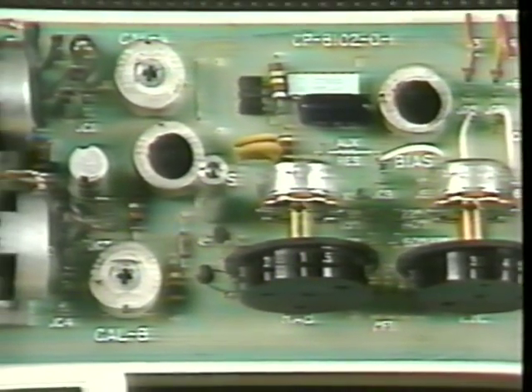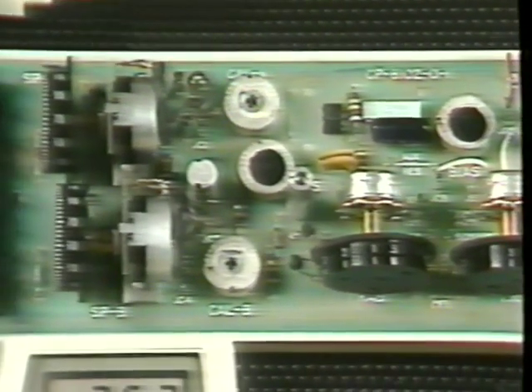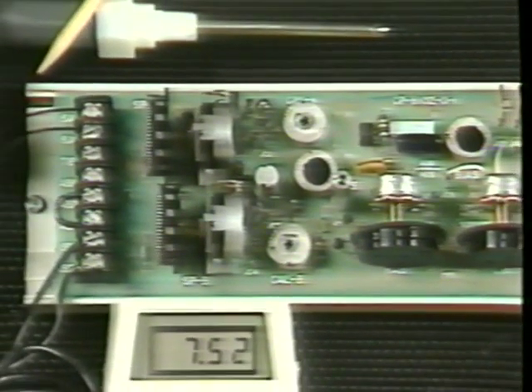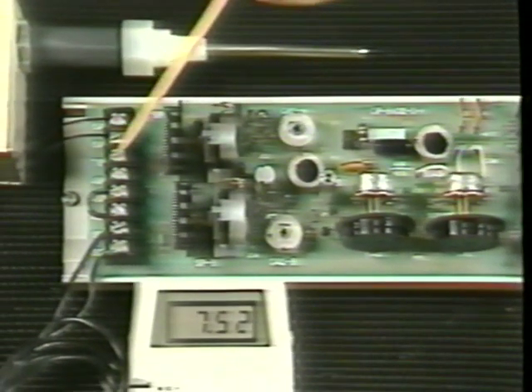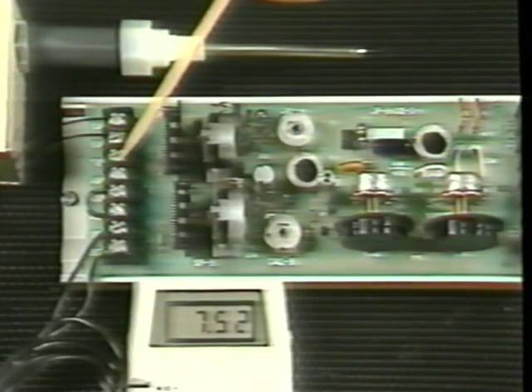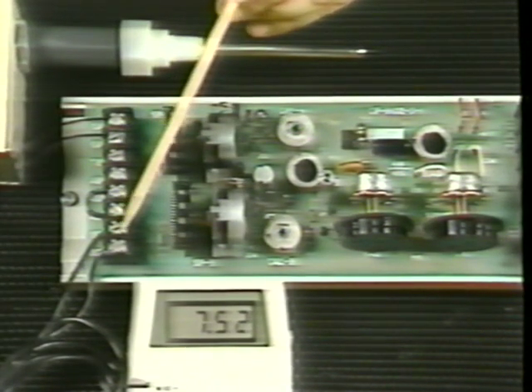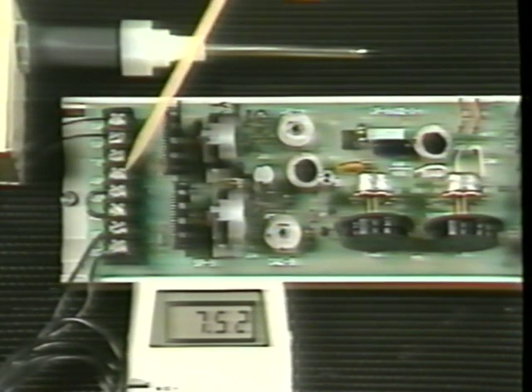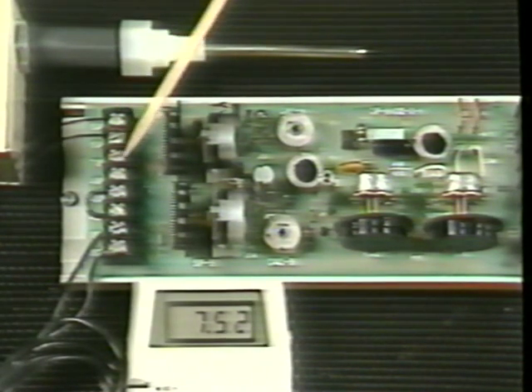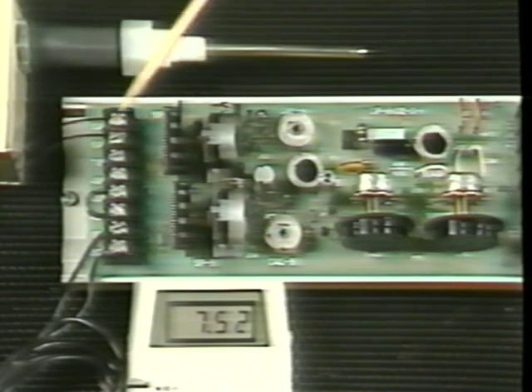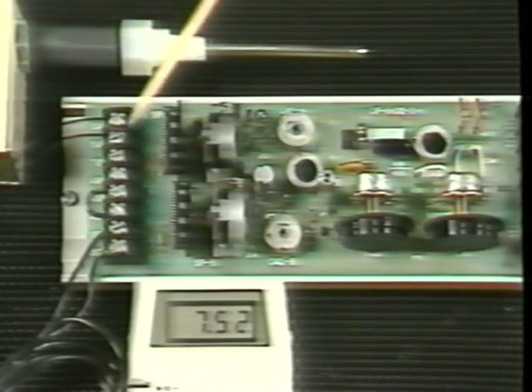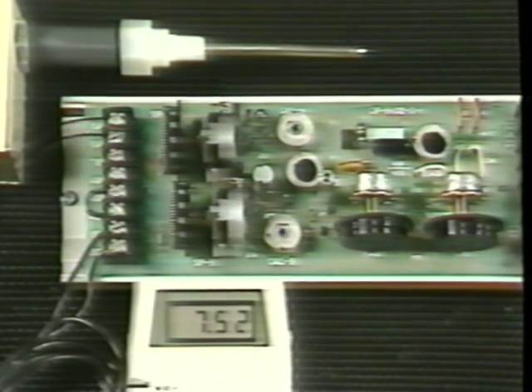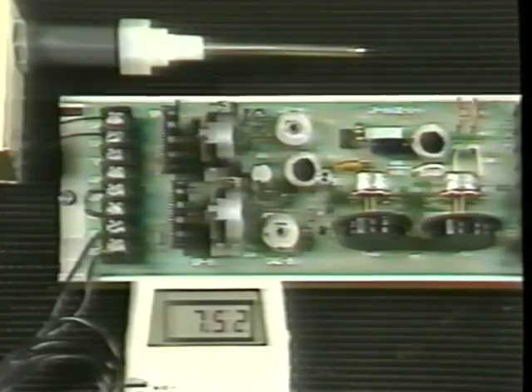If an additional sensor is being input through a multifunction bridge at AB1, that will remain off until B is calibrated. Then that multifunction bridge input will be restored and the bridge itself will be calibrated. In all cases, we calibrate to the same output voltage. In this example, the standard 7.5 volts DC.